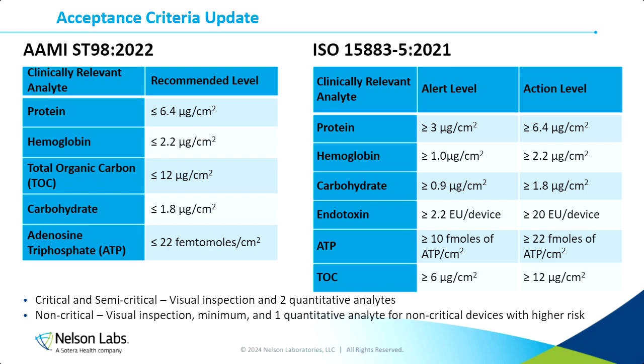And when it comes to non-critical devices, at minimum, they just need that visual inspection. But in ST98, there is a section that lists some of these higher risk non-critical devices, so, a higher risk of cross-contamination between patient use or for accumulation of soil maybe. And in those cases, it may be appropriate to evaluate 1 analyte, such as protein.